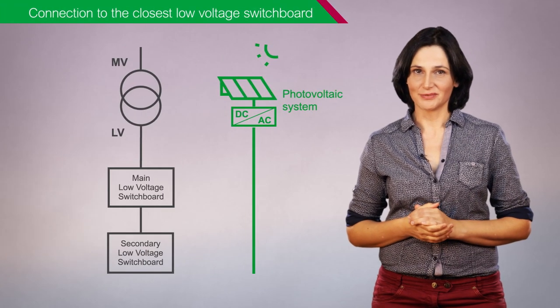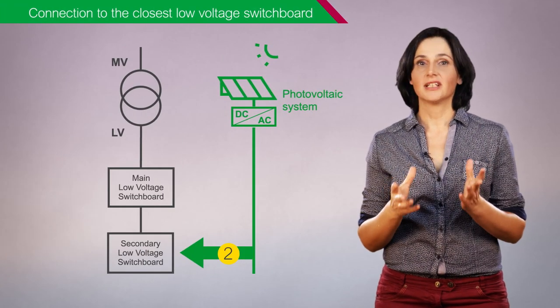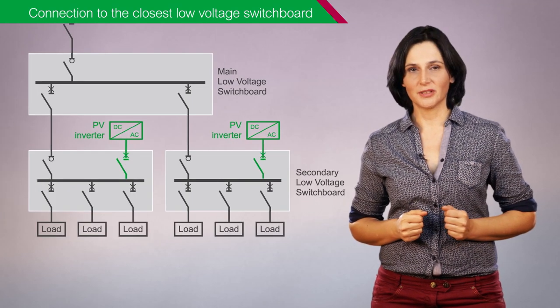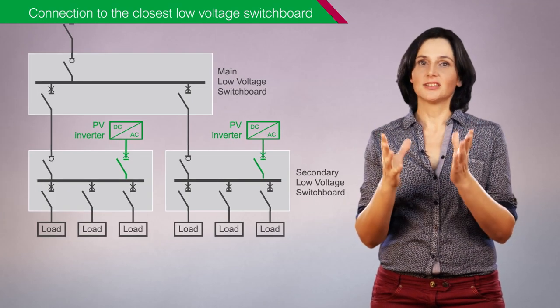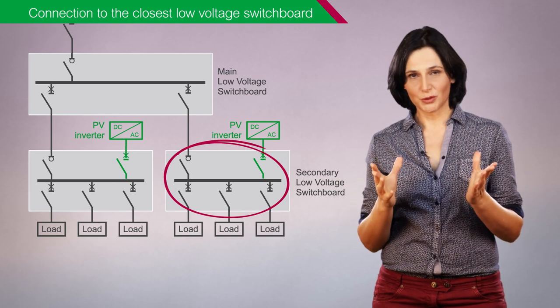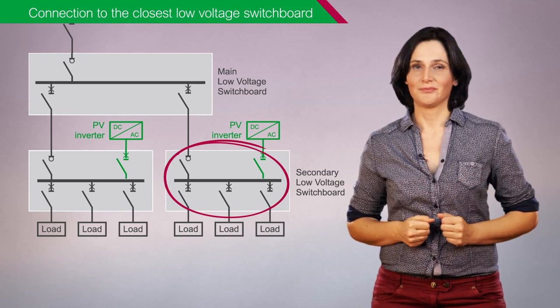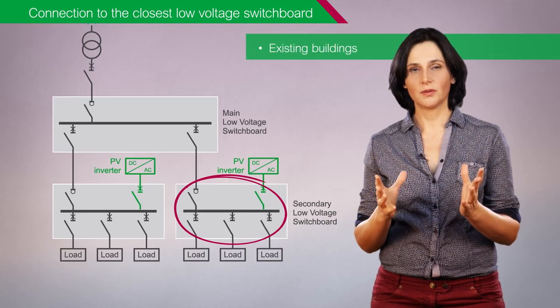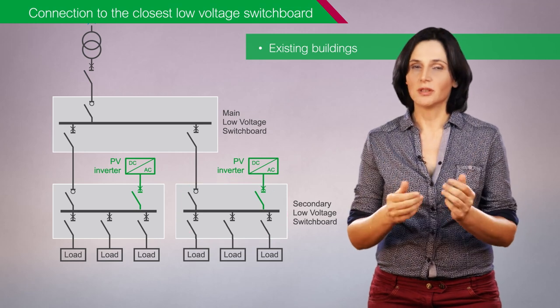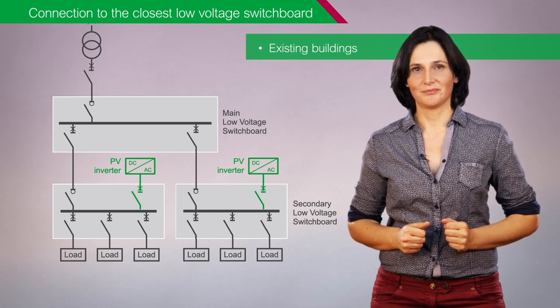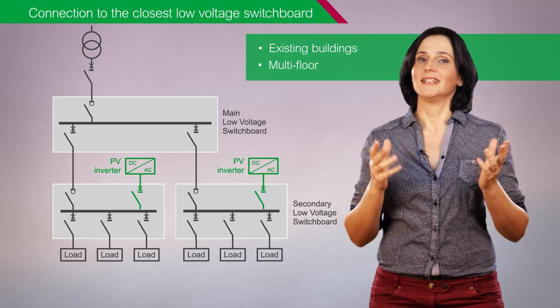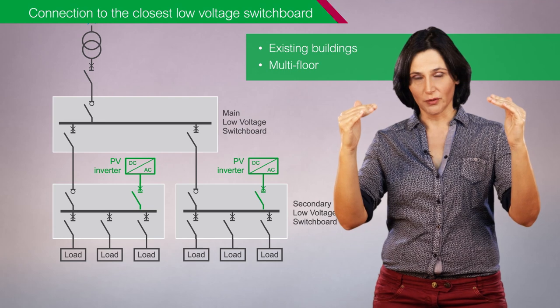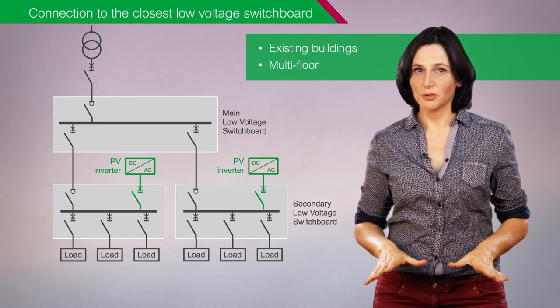Second architecture. In this architecture, the photovoltaic production, here presented with a single photovoltaic inverter, is connected to a secondary low voltage switchboard, usually the closest one. This architecture is suitable for existing buildings where the photovoltaic production is much lower than the building consumption. It's also used for multi-floor existing buildings where the photovoltaic production, usually on the roof, is far from the main low voltage switchboard.